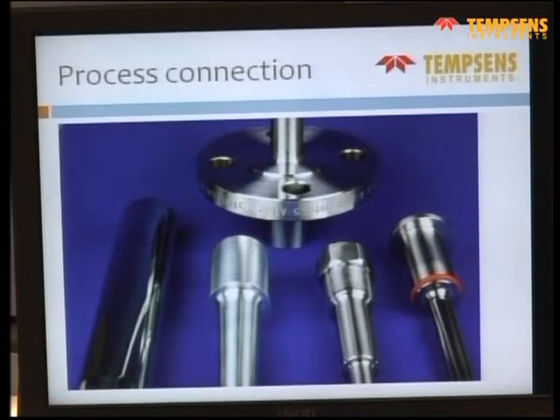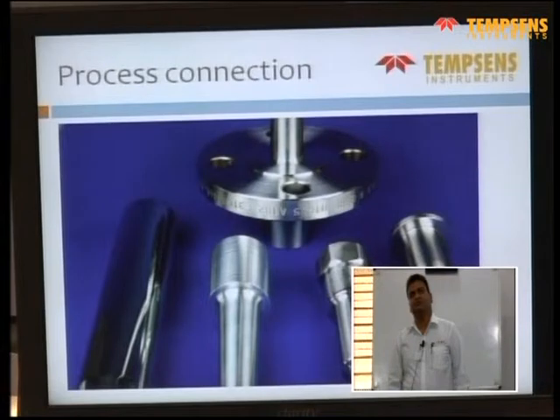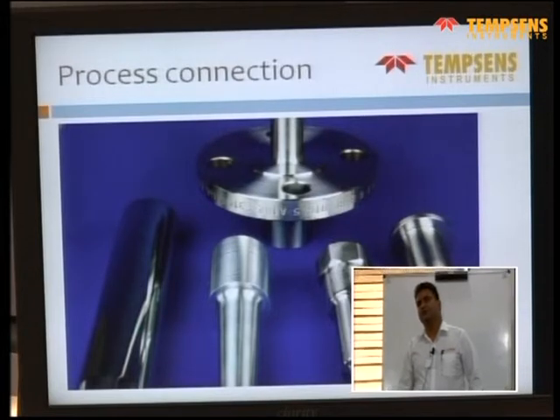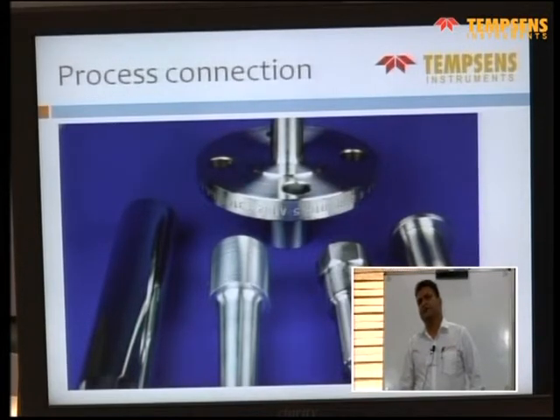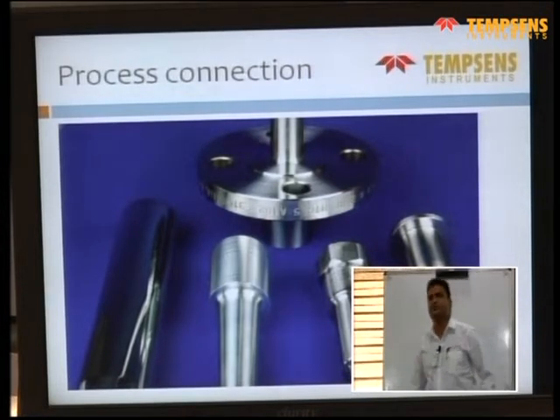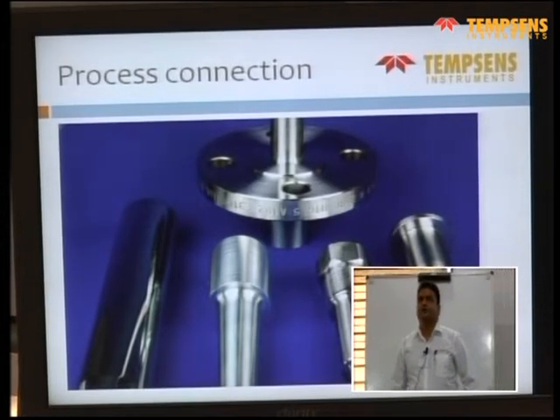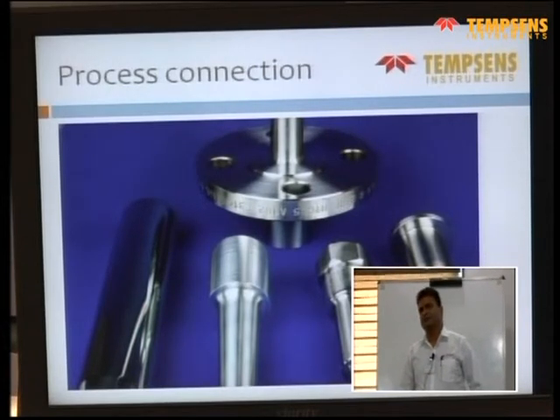As we see here, there are different kinds of process connection. You can see a flange construction, then a welded construction, where the thermowell is welded onto the process, and the second one at the bottom is also a welded construction. Then we have the screwed connection, and the fourth one is a connection for easy replaceability in a vacuum kind of furnace. So there can be different process connections according to the requirement of the process. All these are available from the manufacturers of these sensors and thermowells.